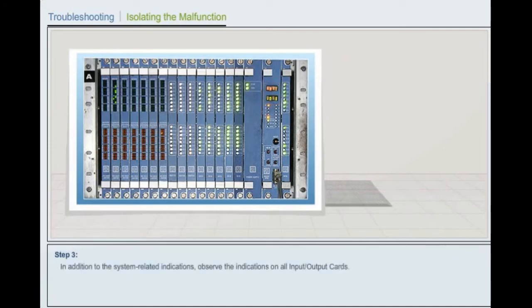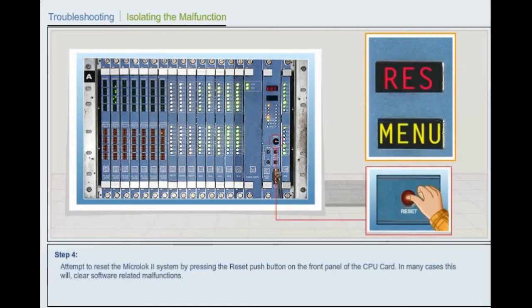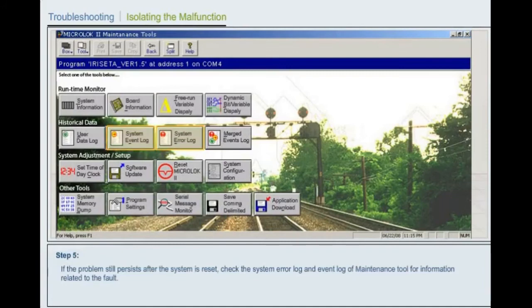Step 3. In addition to the system-related indications, observe the indications on all input-output cards. Step 4. Attempt to reset the Microlok 2 system by pressing the Reset push button on the front panel of the central processing unit card. In many cases, this will clear software-related malfunctions. Step 5. If the problem still persists after the system is reset, check the system error log and event log of the maintenance tool for information related to the fault.